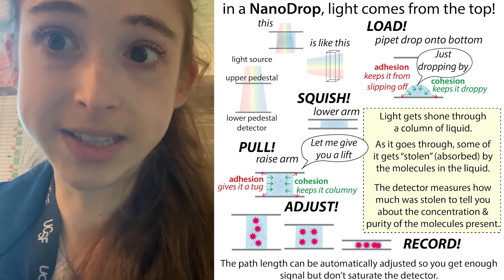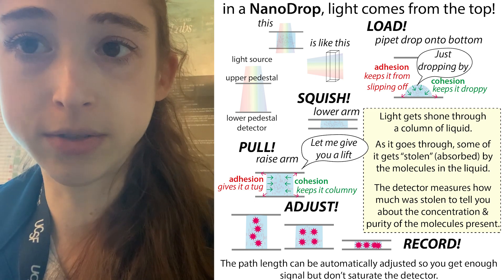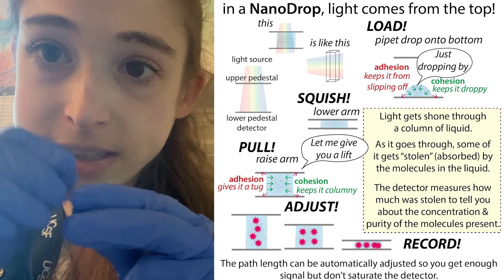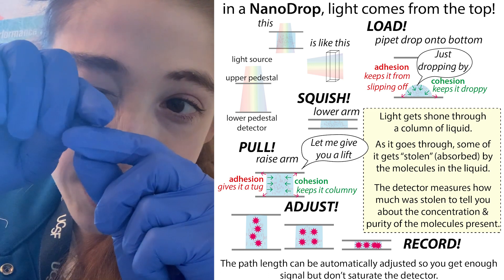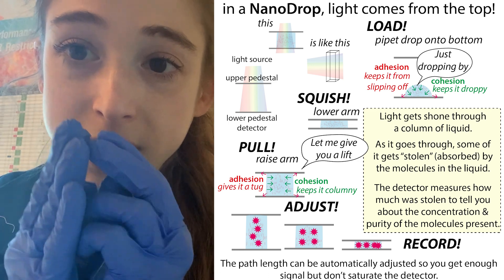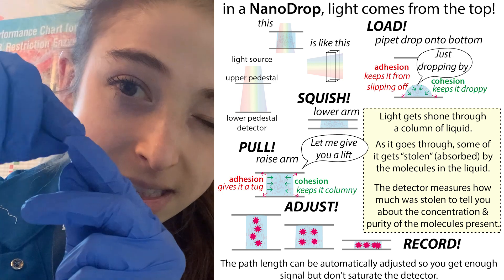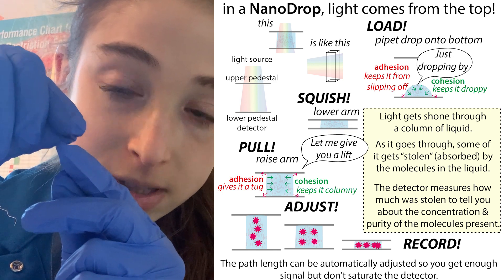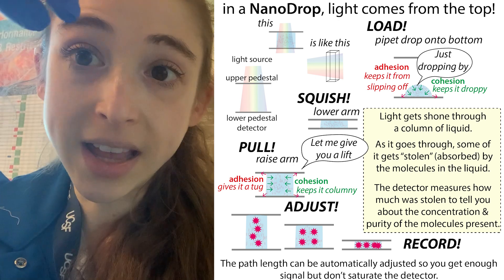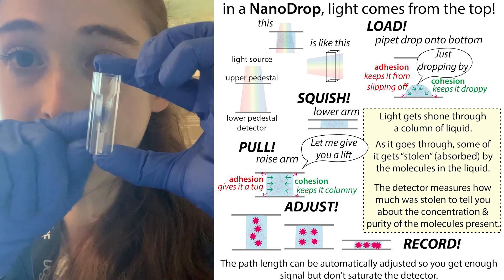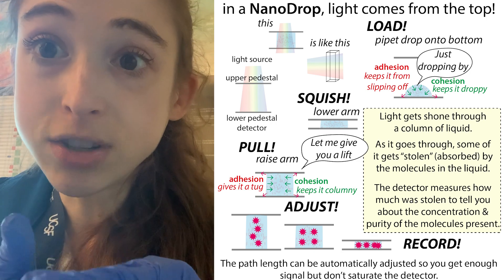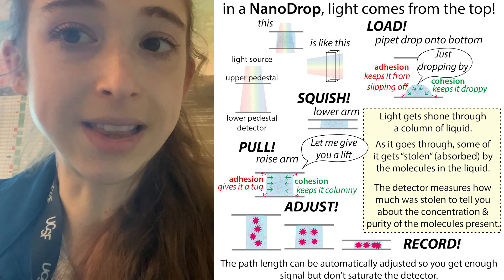The nanodrop is able to form that column because water is really sticky - both for itself and for surfaces. You get adhesion where it sticks to the metal parts on the top and the bottom, and cohesion where water molecules stick to other water molecules. When it's stuck to the bottom and the top and pulls up a little, you get this column. Then the light shines down through the top - unlike a cuvette where the light goes through the side - and a detector below measures how much of that light is absorbed.